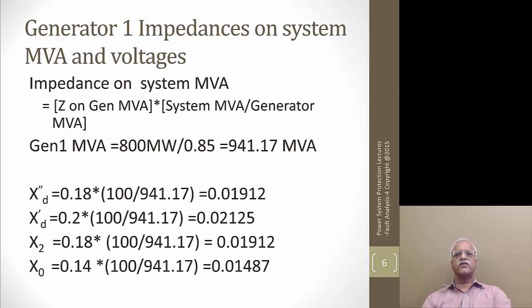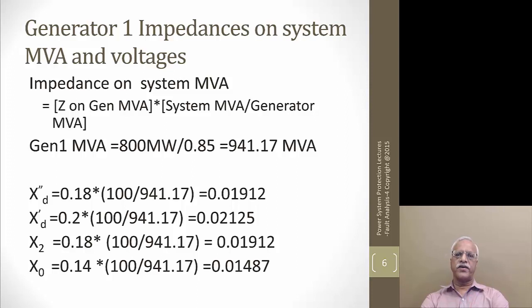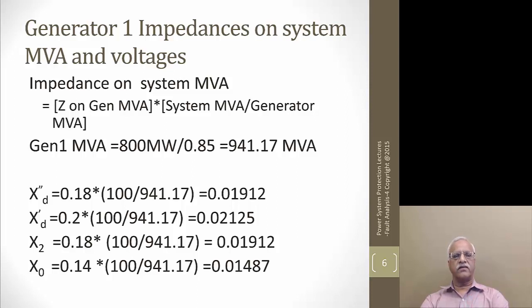To convert generator impedance to system MVA and voltages: Z of the generator on generator MVA multiplied by system MVA divided by generator MVA. The rated MVA of generator one is 800 megawatts divided by 0.85 power factor, which gives 941.17 MVA. So the sub-transient reactance on 100 MVA base is 100 divided by 941 times 0.18, which comes to 0.01912 per unit. Negative sequence is also 0.01912, and zero sequence is 0.01487.